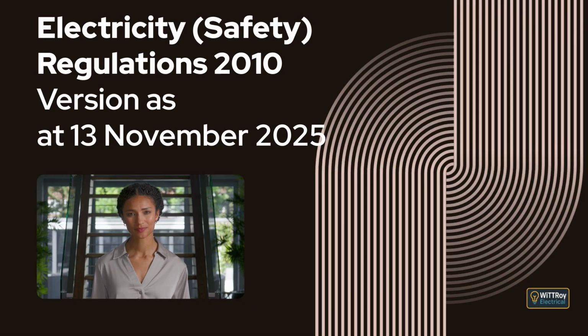The regulation explains that general prescribed electrical work is not treated as complete until a certificate of compliance is issued, and that high-risk prescribed electrical work is not treated as complete until a certificate of compliance, along with any required record of inspection, has been issued. It also explains that a person issuing a certificate of compliance, or an electrical safety certificate, may rely in good faith on certificates of compliance issued within the previous 6 months for work done on the same installation or part installation.